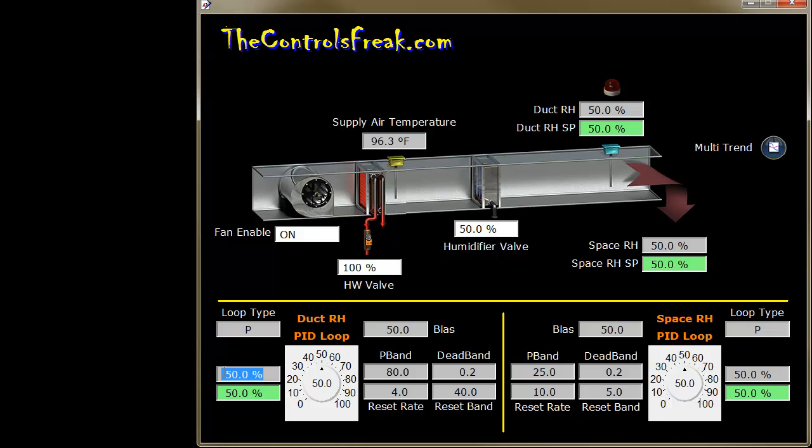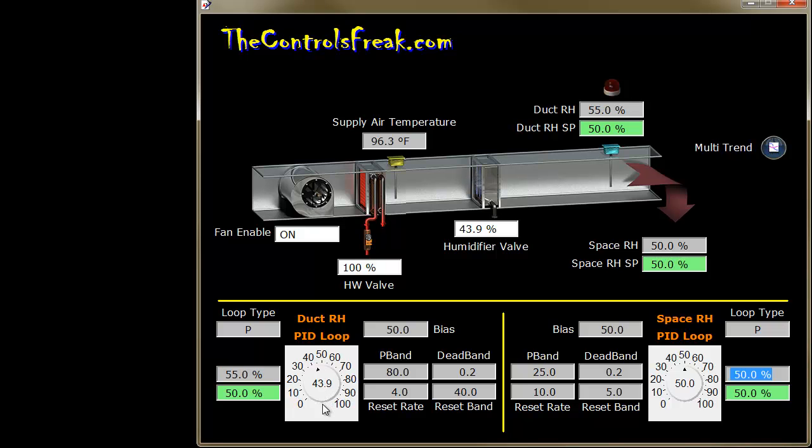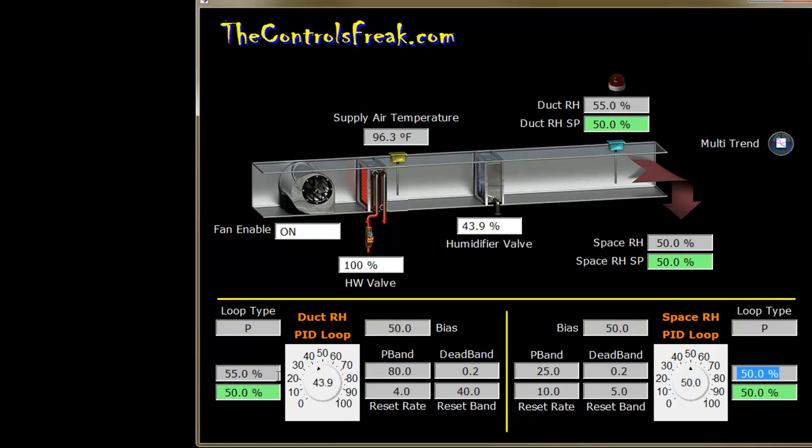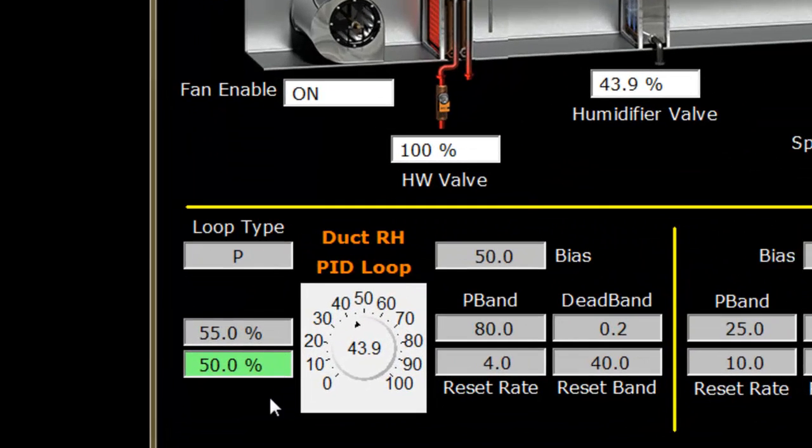If you remember, we set this to 55% relative humidity and noticed the PID loop controller would go to a set amount—in this case 43.9%—and stay there. If the input didn't move, neither did the control loop. Now we're adding fine-tuning adjustments so the input will arrive near the desired set point.